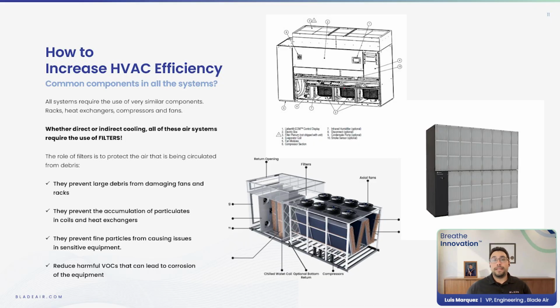As you can see, at the top, we have a CRAC unit with filters at the top. There's 10 filters in that specific unit. On the right, we have our fan wall, which, in my opinion, calling it a filter wall might be more appropriate. And at the bottom left, we have an air economizer with a filter rack for the air coming in. Filters are an essential part of all these types of HVAC systems, data center or otherwise. The air filters are there to help for a few reasons.